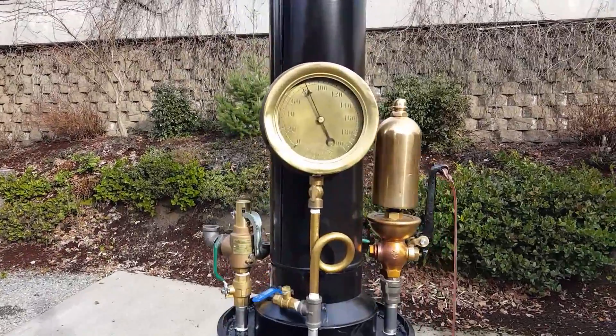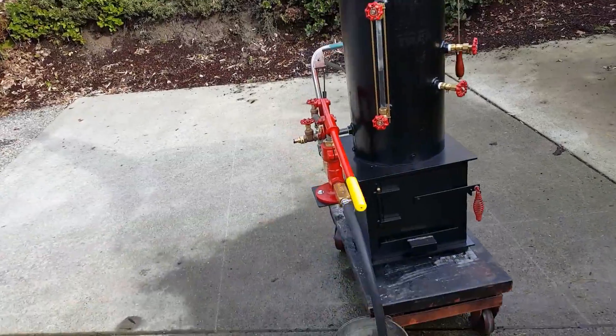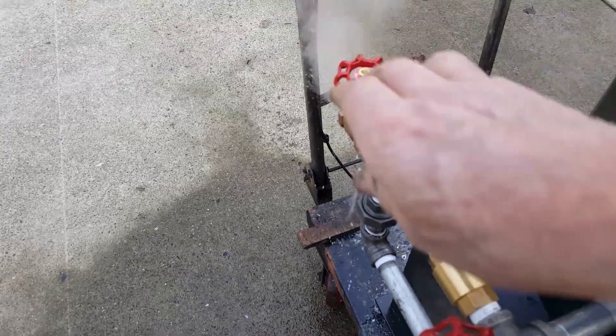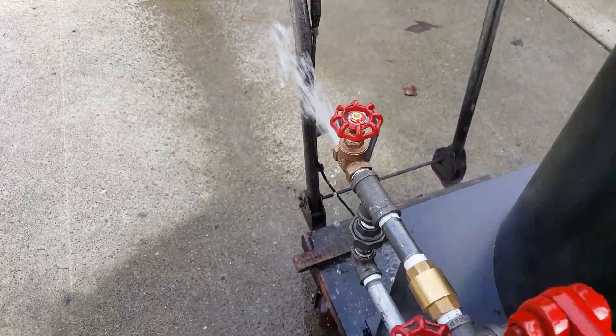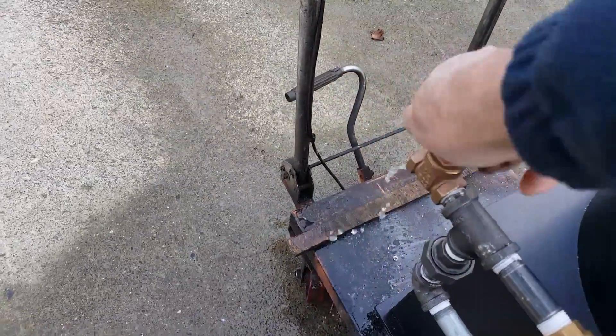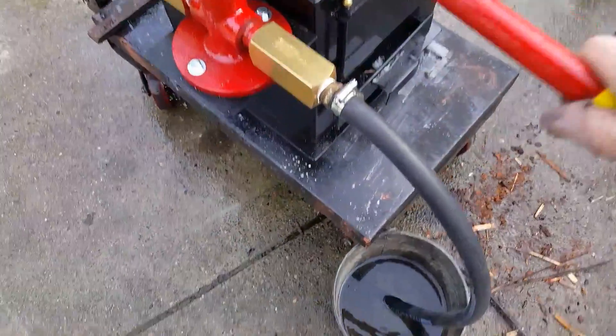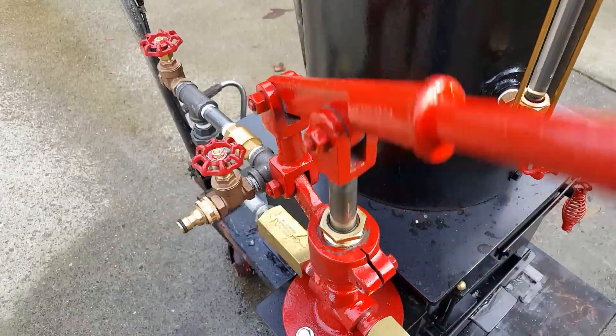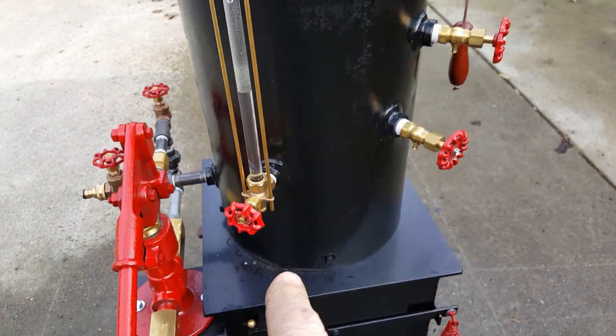About 85 — yeah, that's good. The hand pump is right here, airlock valve is right here. That pop-off valve is leaking a little bit. You get all the air out of the pump if there is air in it; shut off the valve and everything that's pumping now goes right from my little deal into the boiler. Water sight glass right here — keep your water about halfway.